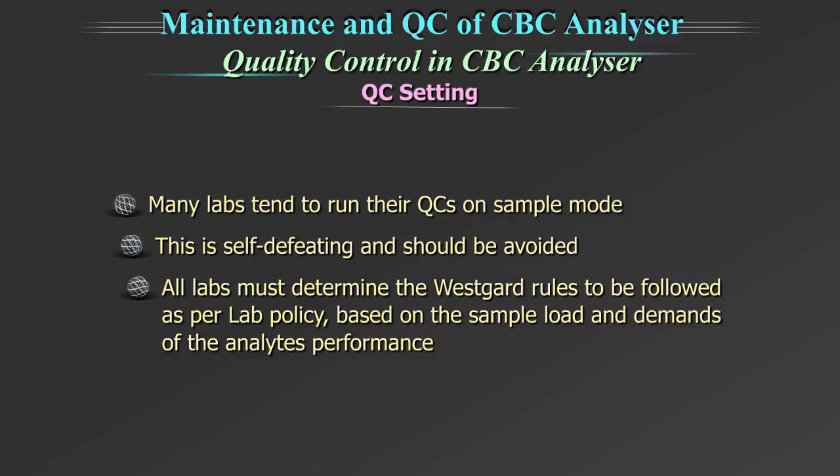Many labs tend to run their quality control on sample mode. This is self-defeating and should be avoided. All labs must determine the Westgard rules to be followed as per lab policy, based on the sample load and demands of the analyte performance.